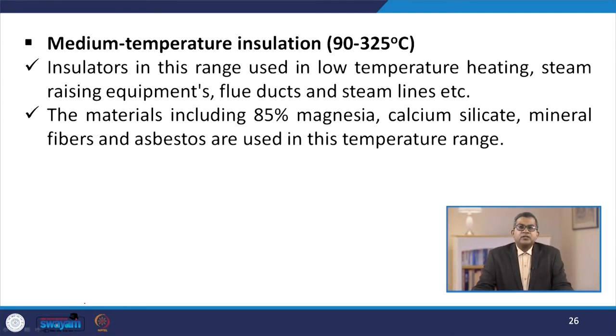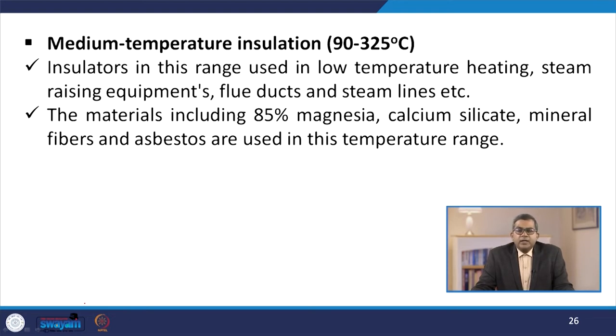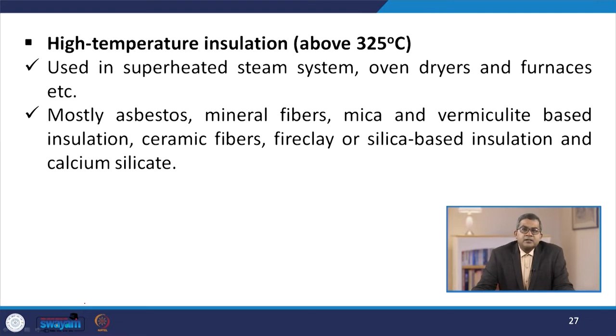Medium temperature insulation ranges from 90 to 325°C, used in low-temperature heating, steam-raising equipment, flue ducts, and steam lines. Materials including 85% magnesia, calcium silicate, mineral fibres, and asbestos are used in this temperature range. The last category is high temperature insulation, above 325°C, used in superheated steam systems, oven dryers, and furnaces. Materials include asbestos, mineral fibre, mica, vermiculite-based insulation, ceramic fibres, fire clay or silica-based insulation, and calcium silicate.